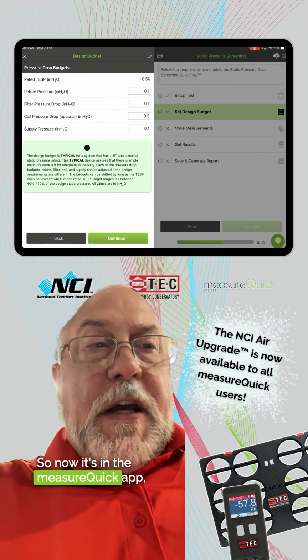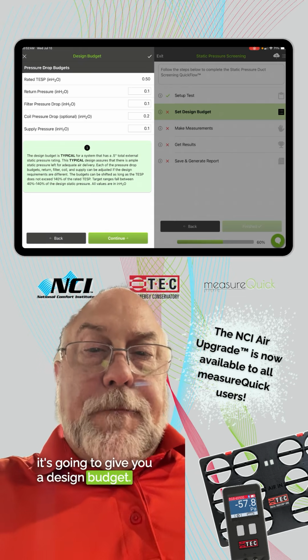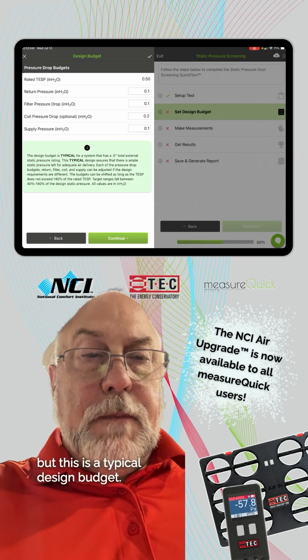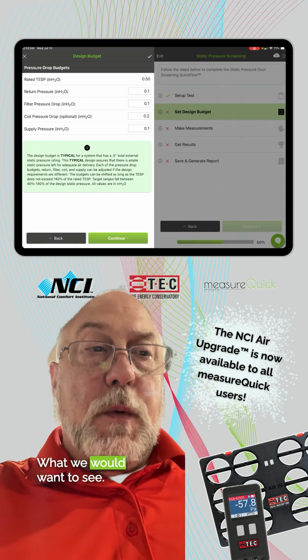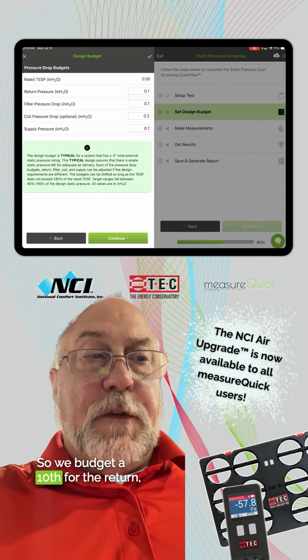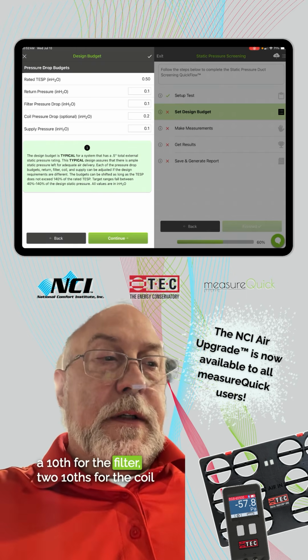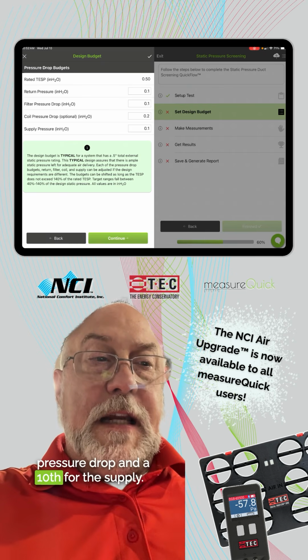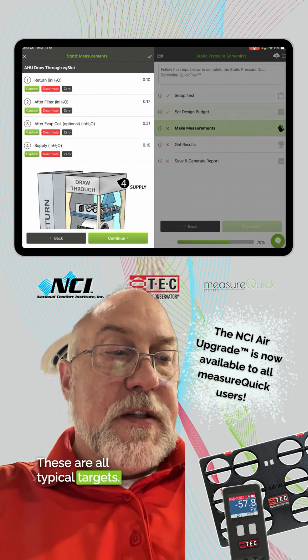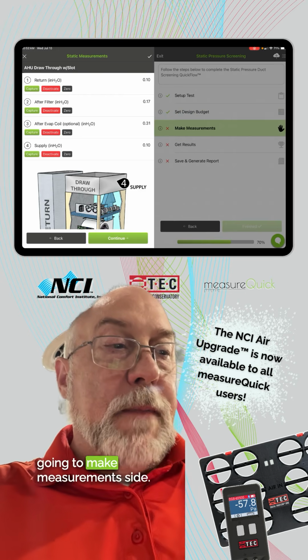So now it's in the MeasureQuick app, it's going to give you a design budget. That design budget can be changed, but this is a typical design budget, what we would want to see. So we budget a tenth for the return, a tenth for the filter, 2/10 for the coil pressure drop, and a tenth for the supply. These are all typical targets. So I'm going to hit continue, and we're going to make measurement side.